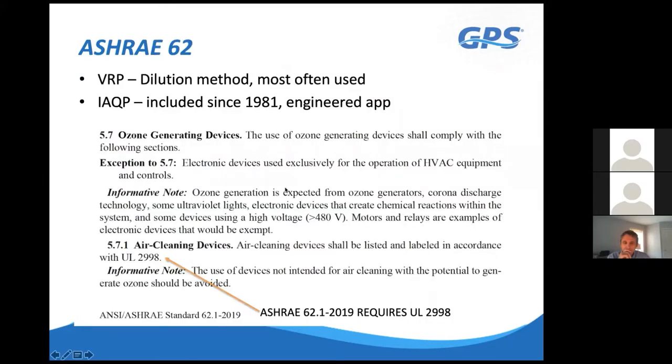Using ASHRAE Standard 62's indoor air quality procedure, you can clean the building air with this technology, recirculate it, and reduce outside air requirements. We have software that calculates both the Ventilation Rate Procedure and the Indoor Air Quality Procedure. What's nice is that you don't need any more data to run the IAQP calculations than you already need to design with the VRP.